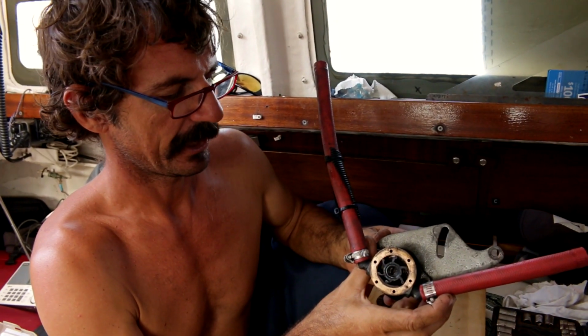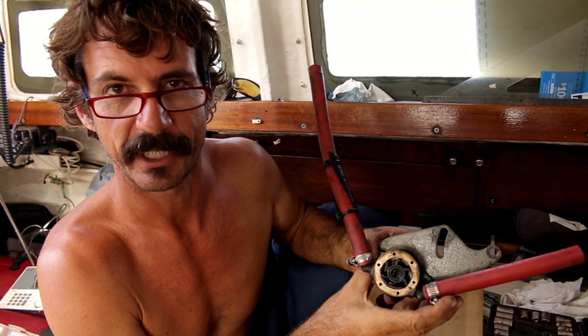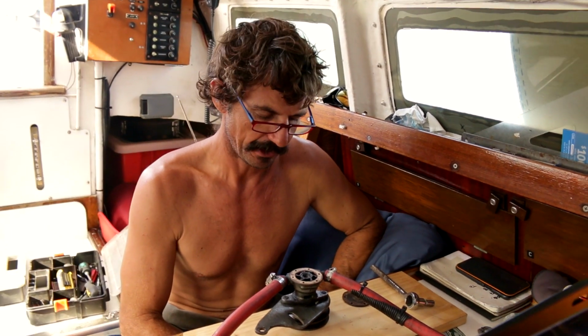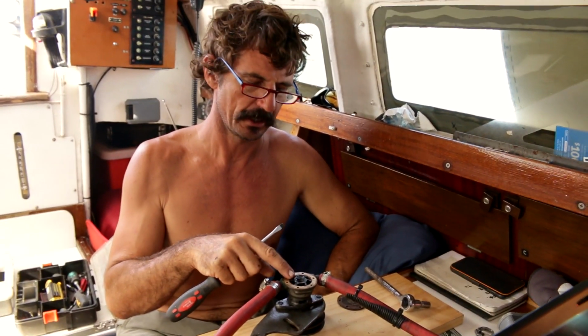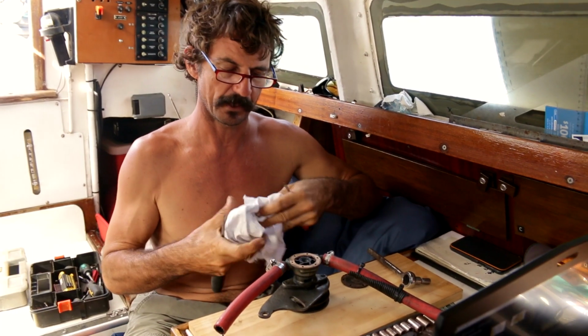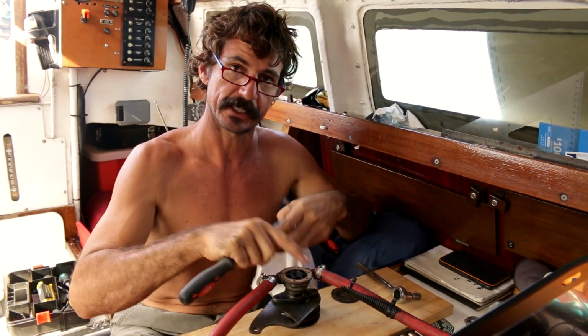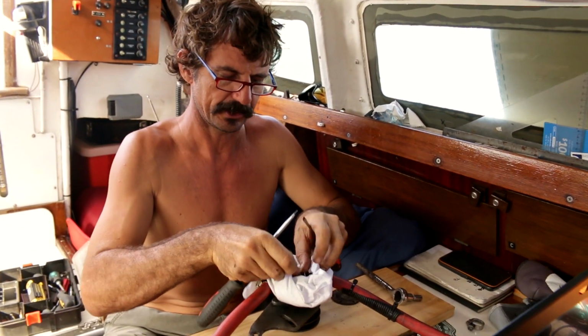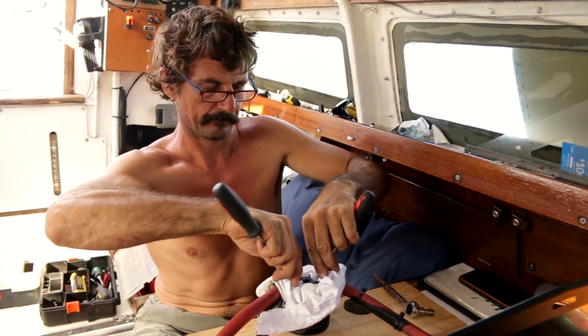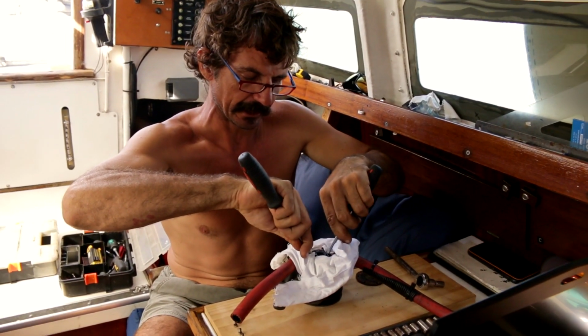That's all right. We've got another impeller complete that's sitting somewhere, and I'm just going to dig it out. So we'll pull this out and we'll just replace it. So it should be fairly straightforward. Okay, now, not everyone has an impeller puller in their workshop or on their boat. So there is another way, using two screwdrivers to dig in and pry that up at the same time. But what we do want to do is make sure that the screwdrivers don't dent this face here, because that's a sealing face. So I'll put some rags there on the fulcrum of these screwdrivers.